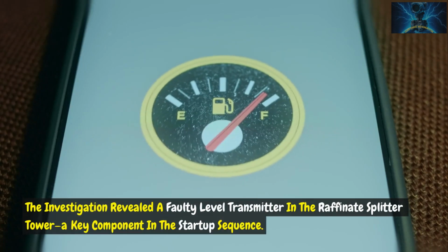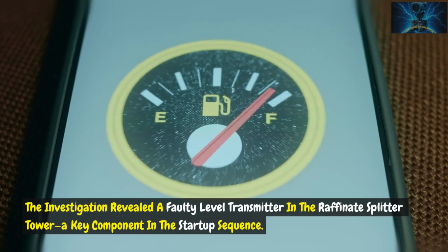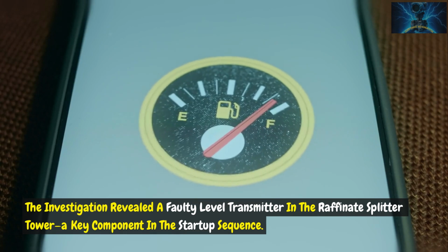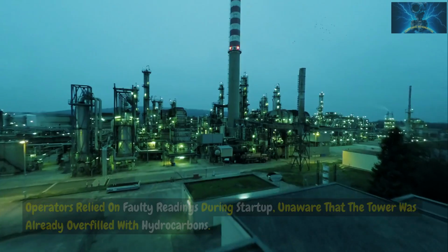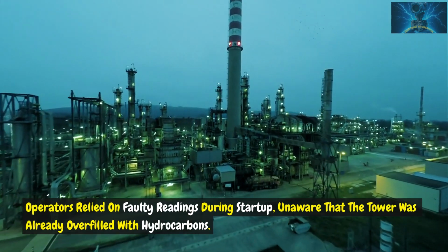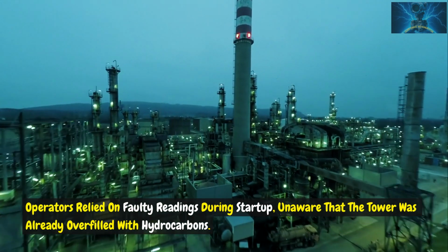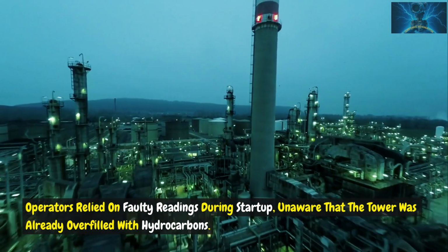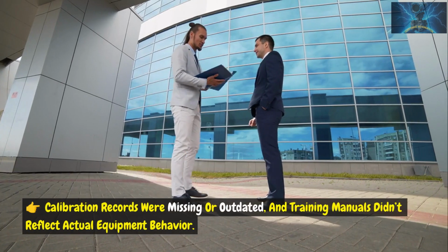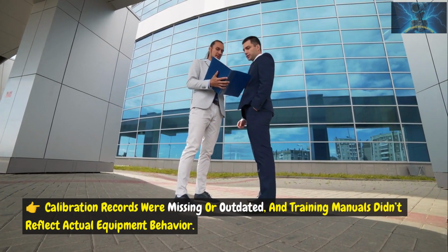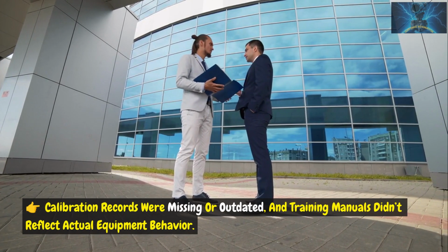The investigation revealed a faulty level transmitter in the raffinate splitter tower, a key component in the startup sequence. Operators relied on faulty readings during startup, unaware that the tower was already overfilled with hydrocarbons. Calibration records were missing or outdated, and training manuals didn't reflect actual equipment behavior.